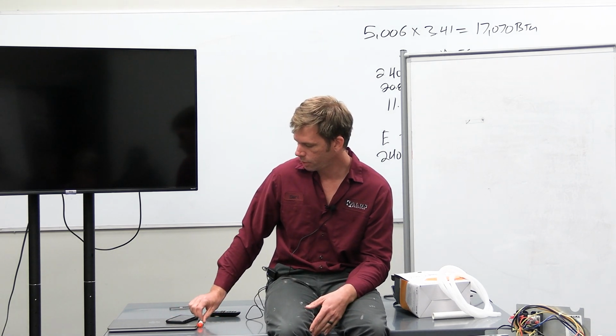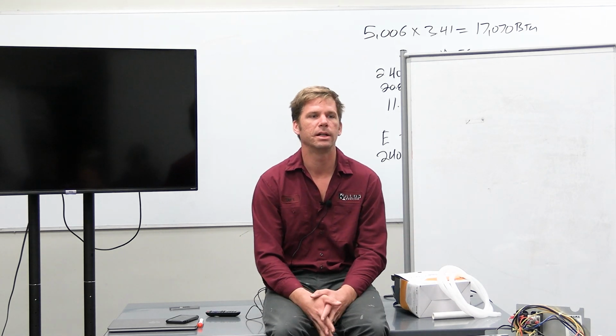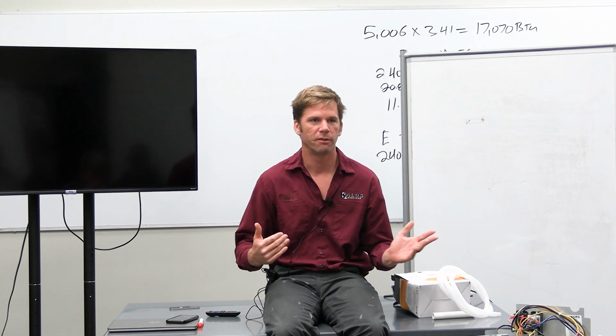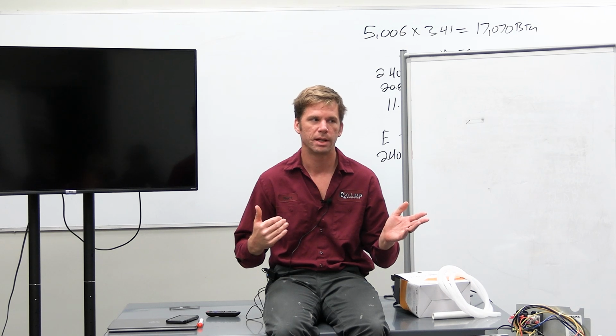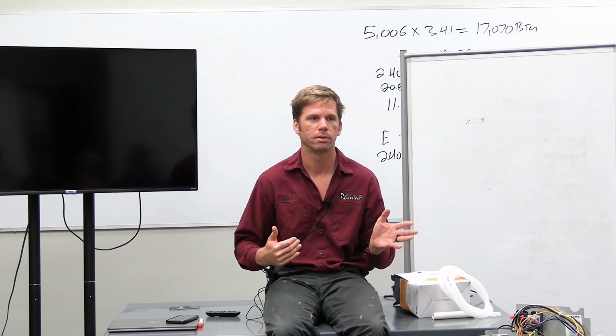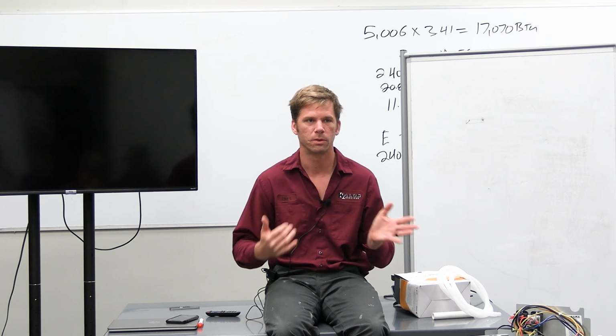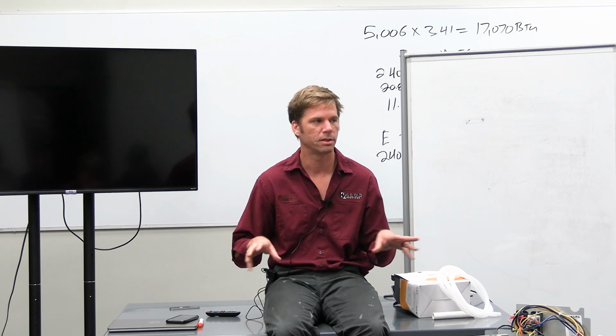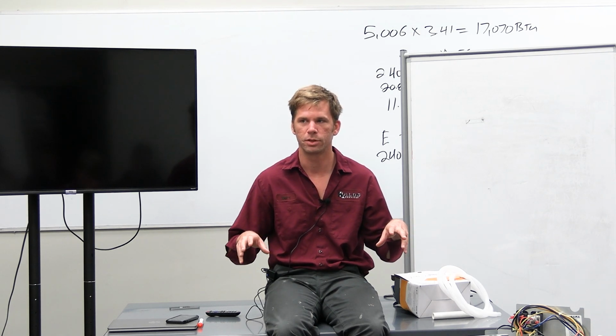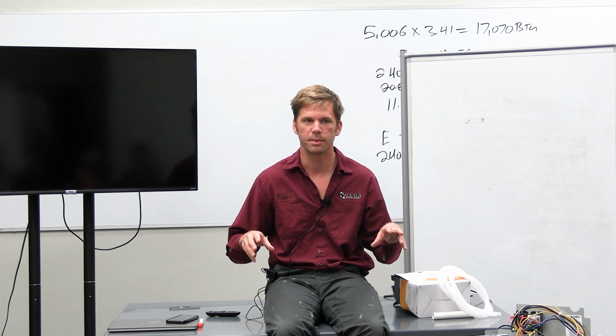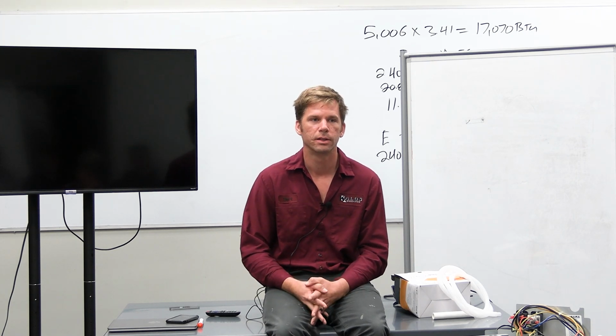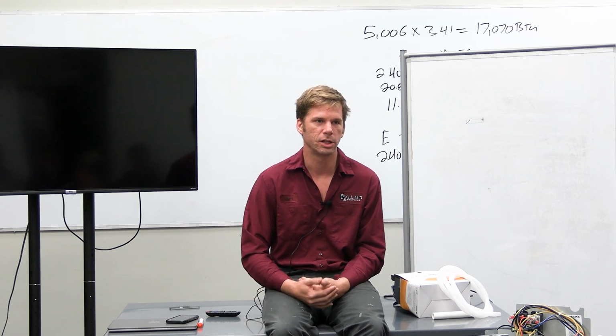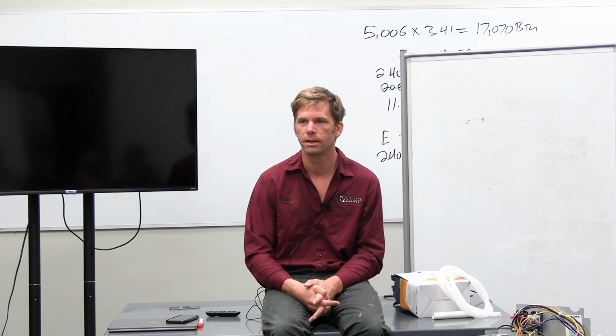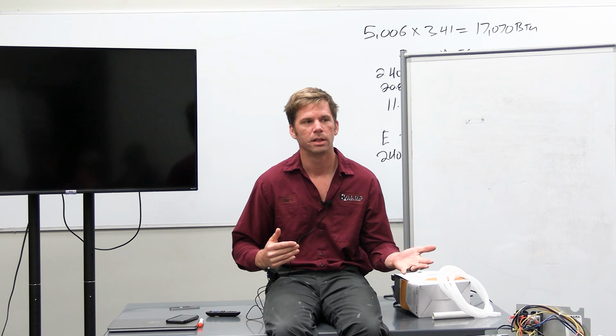Okay, so final note then, when you're doing a maintenance, we've just ordered a maintenance on the gas heater. Open the panels to see if bugs need to be cleaned out, animals, lizards, rats, whatever. Check behind the board for a lizard. Check for evidence the rats have lived in there. If they have, then we just need to look at wiring issues. A lot of times, rats just chew through wires. So you're pulling error codes or stuff like that, and the issue is some critter, squirrel, rat has gotten in there. So always open your heater to see if there's anything that needs to be cleaned up or tightened up.